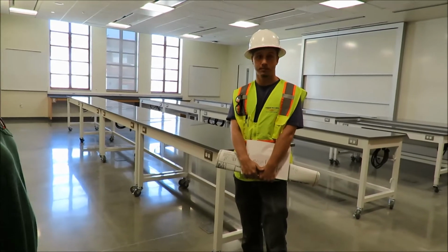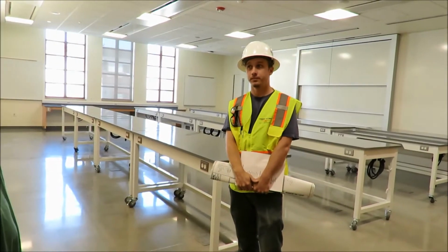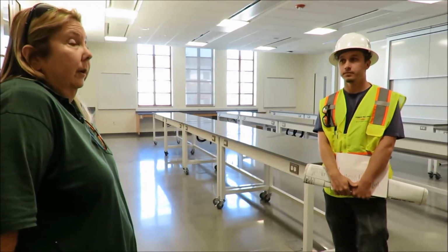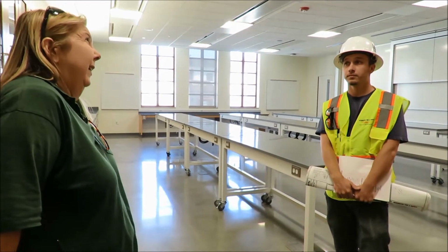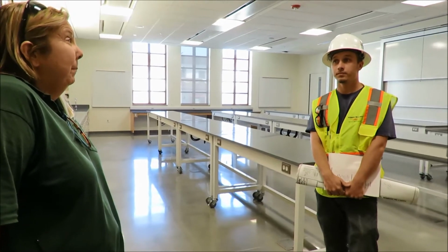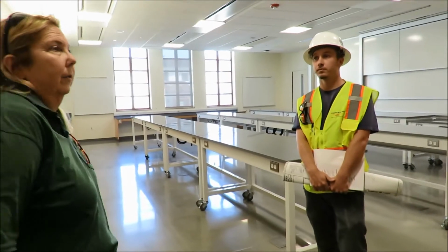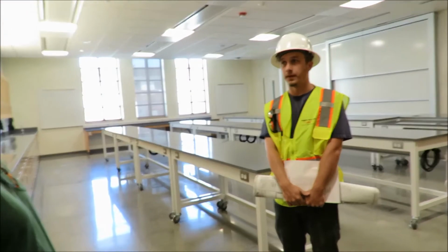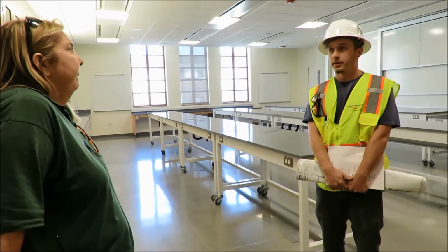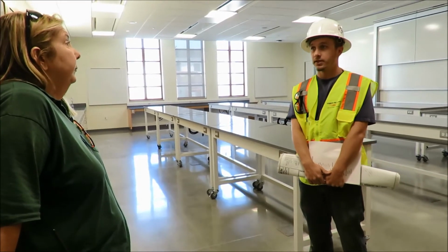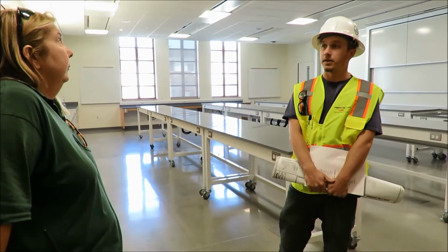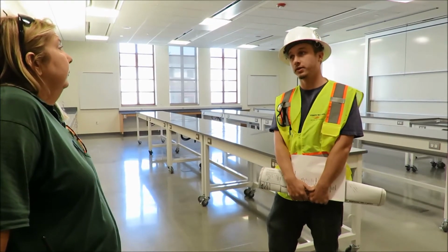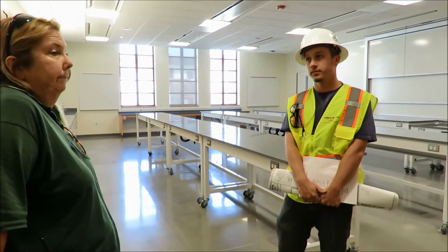Correct, that's waking up the guy with the headsets on. And it's different than in Aliso Hall, because Aliso Hall in a room like this has, I think, maybe 2 or 3 smoke detectors, and they get drilled pretty often, but they've been better. It's always something that can be changed later on if they're uncomfortable with the amount of coverage, but essentially, being a fully sprinklered building, they aren't required to have the smoke detectors.